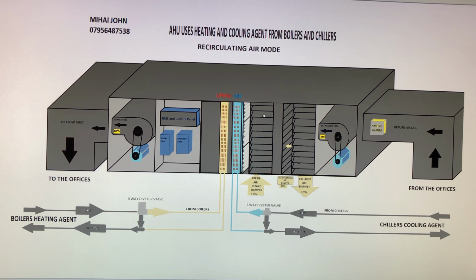And then if you go a little bit to the right hand side again, you'll get to the dampers. The dampers will ensure that the right quantity of air will be taken into the building and exhausted from the building, and also will decide how much air will be recirculated through the building. One step further, you'll find the extractor fan.